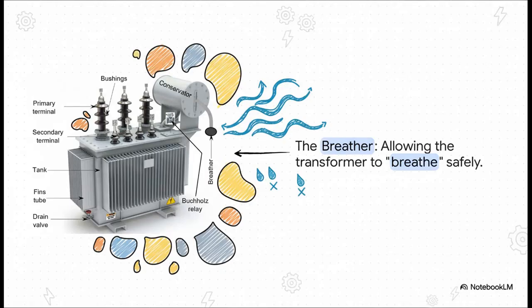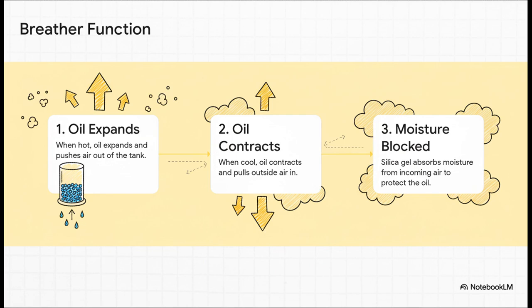As the oil heats up and cools down, it expands and contracts, so the transformer needs a way to breathe air in and out without letting in moisture, which would be a disaster. That's the job of the breather. When the transformer gets hot, the oil expands and pushes air out; when it cools down, the oil contracts and sucks air back in. But that outside air has moisture in it, and water is the enemy of insulating oil, so the air gets pulled through silica gel inside the breather, which acts like a filter, grabbing the moisture before the clean, dry air gets inside.